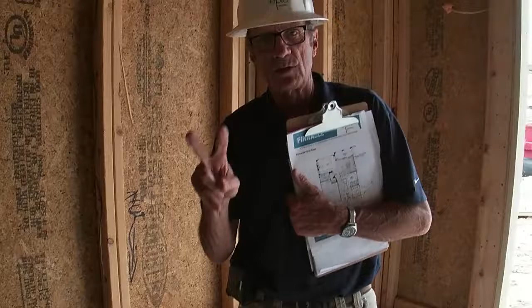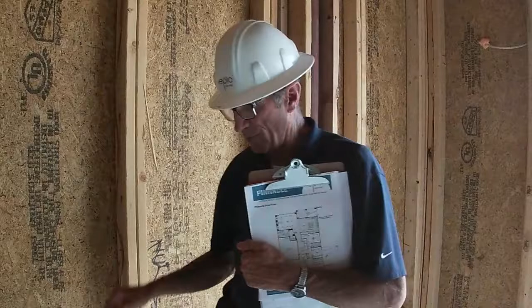This is called a UFER ground, or a secondary means of ground. We have two means of electrical grounding in the house: one is to the water service bond, to the copper underground coming from the street, and the other is to a piece of rebar which goes down through the foundation and into the ground. That's called the UFER ground, or a concrete encased electrode, CEE.